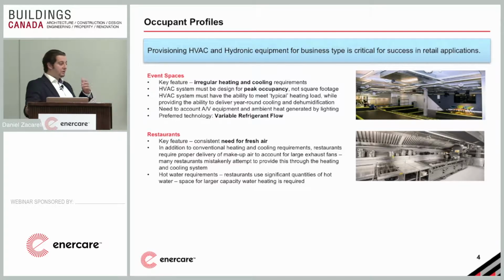I'm sure everybody's been to one of those restaurants where you walk in the door and you try and open it and you need both hands to pull that door open. That's a restaurant that has a big negative air issue. And a lot of people, when they design these spaces that have a lot of exhaust ventilation, don't think about that air being replaced back in.